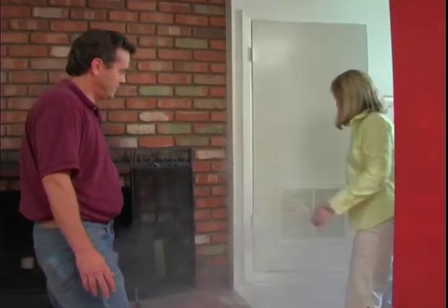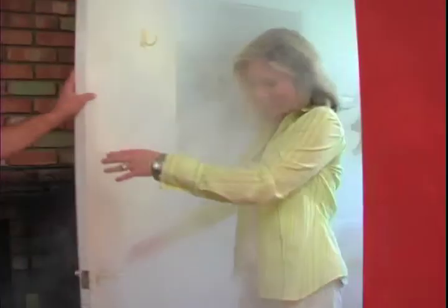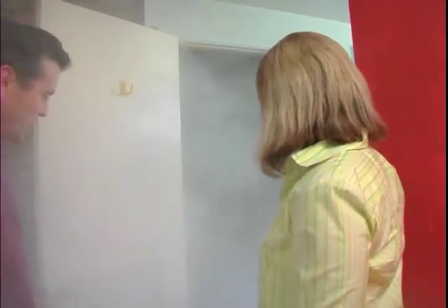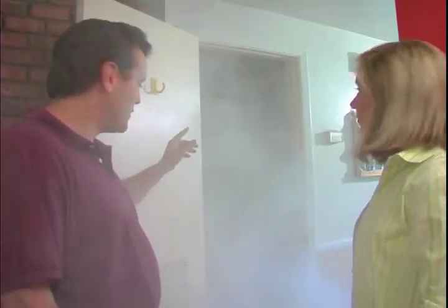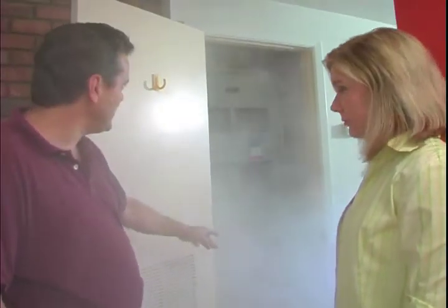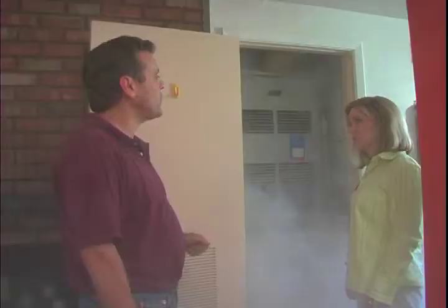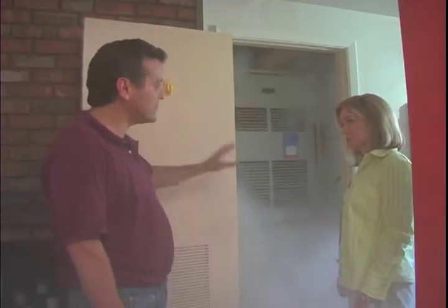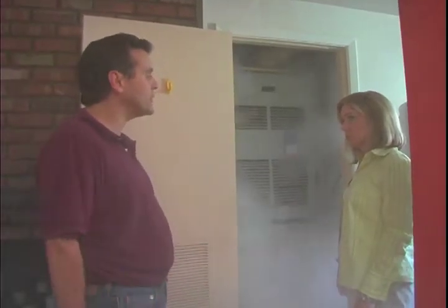Let's take a look inside. Oh my goodness, yeah, this is also leaking quite a bit in here. Looking at it, there are some penetrations through the platform that are leaking, and some old tape that's dried out and falling off. So we have a lot of sealing to do. We do. What we're going to do is replace this system, retest to make sure everything is sealed up properly, and see where we are with the rest of the system.